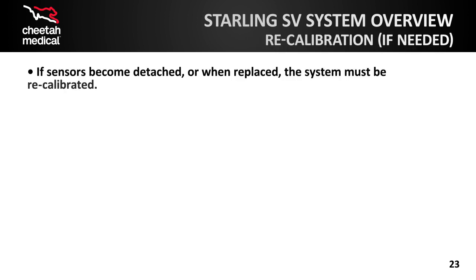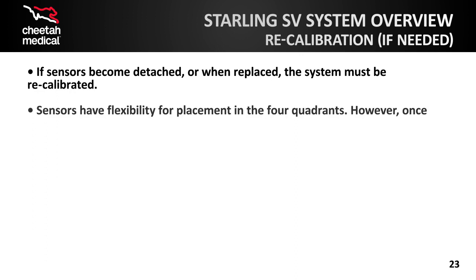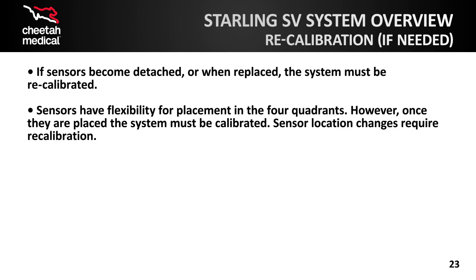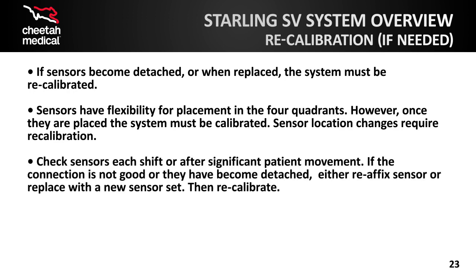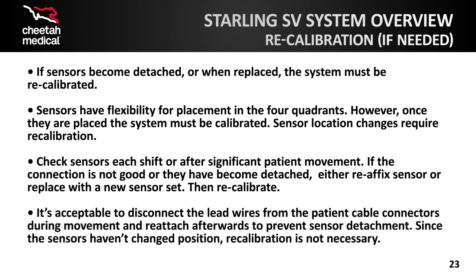Other situations to consider Starling system recalibration: when sensors come off or are replaced, the system must be recalibrated. Sensors have a lot of flexibility for placement within the 4 quadrants. However, once they are placed, the system must be calibrated from that position. It is okay to disconnect the lead wires from the patient cable and reattach afterwards without recalibration. Always check sensors each shift or after patient movement, and if they need reattachment, recalibrate.